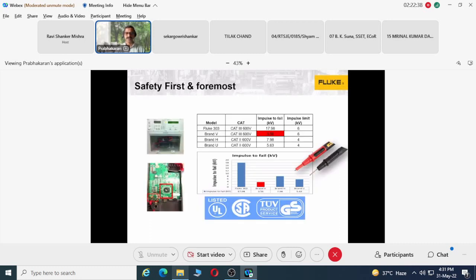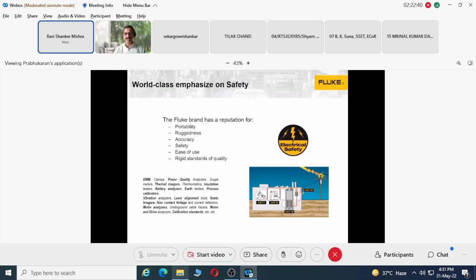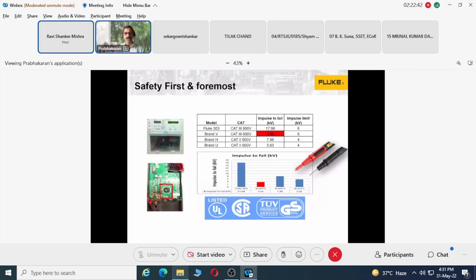Yes, sir. And you will find this rating on the multimeter's body itself. But many a time the low cost models also give that safety rating, like category 3. It will be mentioned there, but they will not have any listing or certificate from a third party. That's why it is better to ask the manufacturer for a listing certificate or a test certificate for this kind of safety, so that you can ensure you are getting a safer product.